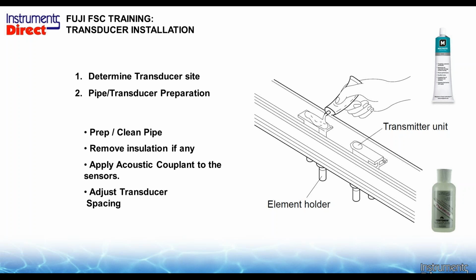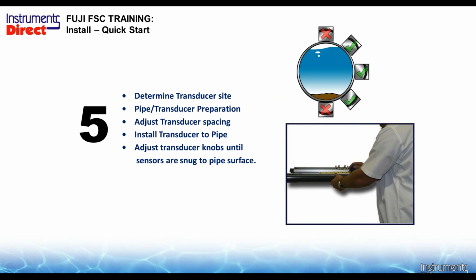That's what the grease is for. The grease, basically, we put some grease on the face of the transducer, toothpaste on a toothbrush amount. The transducer's flat, the pipe is round, so the grease will fill in the pits, and it'll convey the signal from the transducer through the grease into the pipe wall. So then the next step after that is we adjust the spacing that we just got from the program in the flow meter, which is the differential spacing between the 2 transducers.